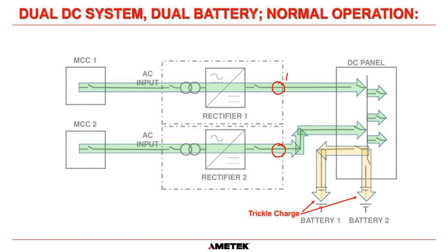So let's say all we care about is that this charger here has 10 amps and this charger here has 10 amps. The only control we have over that current is the voltage out of the charger. So we would have to increase one charger to make sure it supplies 10 amps while the other charger is doing 10 amps. And if we adjust one, that means we are going to change the terminal voltage of the battery.